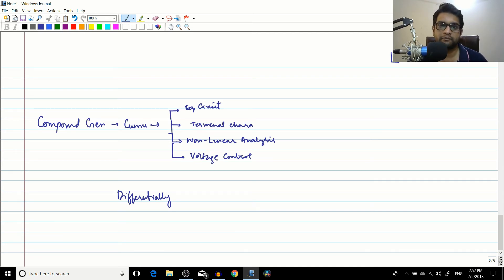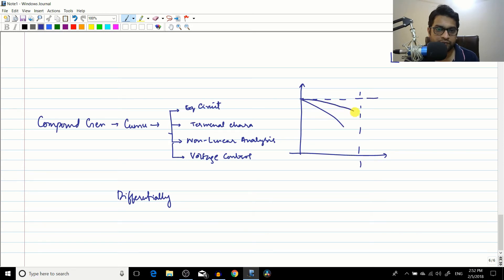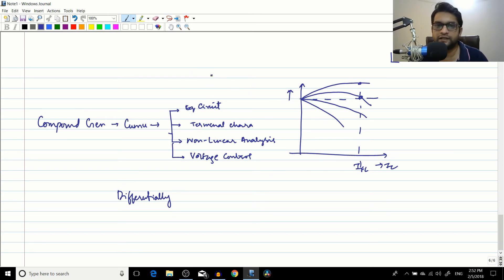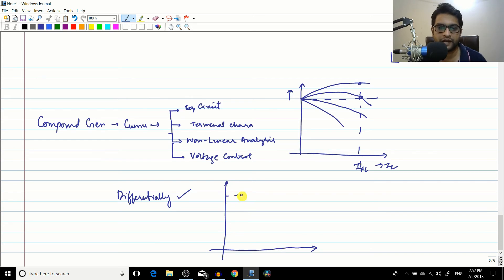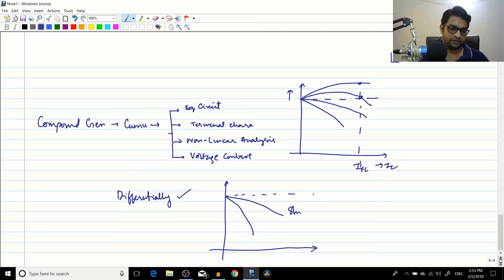The cumulatively compound generator uses the best of both the shunt and series generators. Depending on the degree of compounding: an under-compound generator has slightly better characteristics than the shunt; a flat-compound generator has the same no-load and full-load voltage; and an over-compound generator has a full-load voltage greater than its no-load voltage, achieved by the series winding. Finally, the differentially compound generator has windings in magnetic opposition, giving a very poor, steeply drooping characteristic.